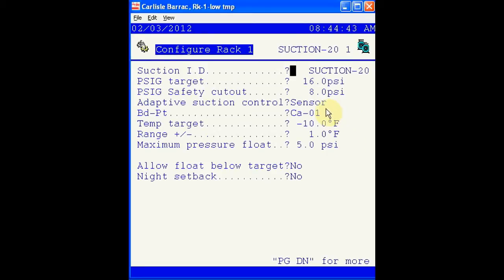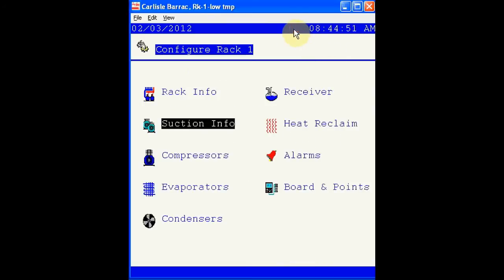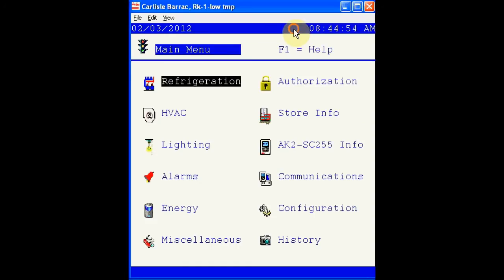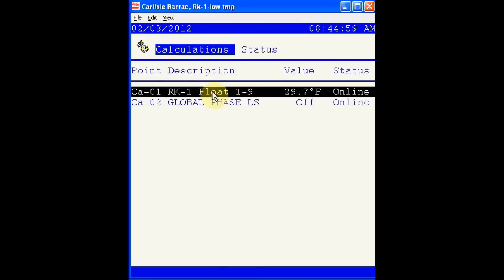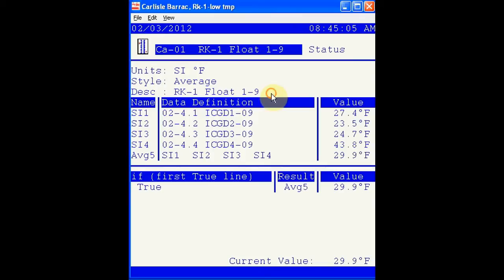We know that this board point is a calculation. Let's take a look at what's really going on in this calculation. Calculation number 1, as you can see, is used for floating. In this calculation, we're taking the average of 4 sensors. In this case, it happens to be ice cream glass doors. The average of these is 29 degrees because the case is in defrost currently.